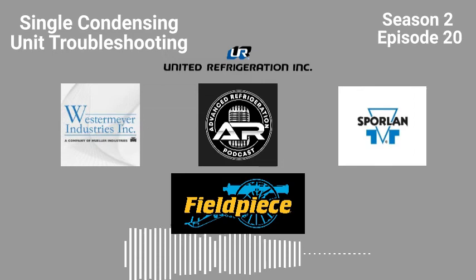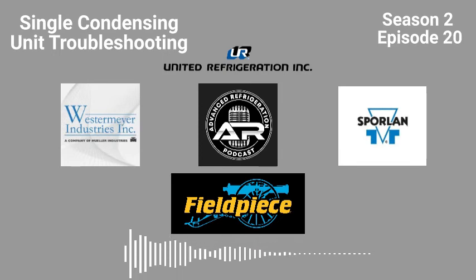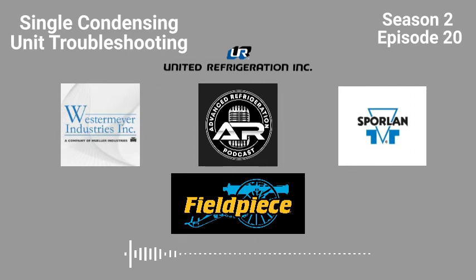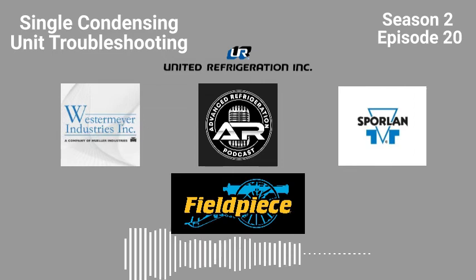But here's the other problem with that. When you get into pulse width modulation, which I don't want to get too into because the next podcast is going to be on this, when you start messing with two different forms of PWM, like you have the pulse width for the case temperature control and the superheat, and you have the pulse width going for the compressor, you're never going to end up with a steady process variable, meaning superheat, ever. You're never, ever going to be able to control that. Even with digital compressors, they do not recommend using digital compressors with anything with electronic.